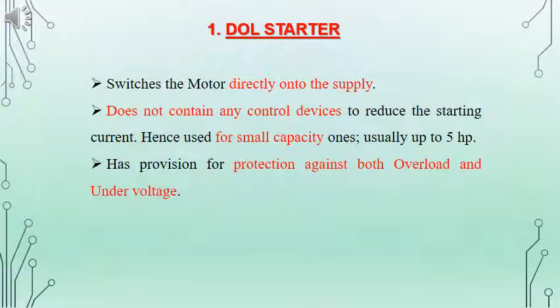We will see what is meant by direct online starting or DOL starter. Here we will be applying the entire voltage, or the rated voltage itself, to the machine. There is no control mechanism in the case of DOL starter, but there will be some protective mechanisms, that is for overload and under voltage. And this starter can be used only for a machine which has small capacity, maybe up to 5 HP.